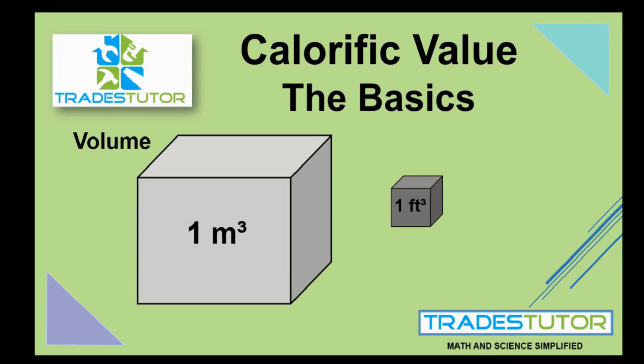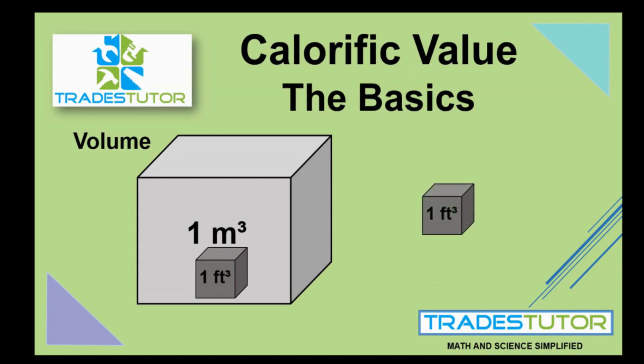Now, this little animation here — these pictures show you that a cubic meter is a lot bigger than a cubic foot, and we know that. But this becomes confusing when we get to calorific values and how to work with it. What you'll see is a cubic foot fits inside a cubic meter. The question is: how many cubic feet fit inside a cubic meter? Well, as it turns out, one cubic meter is equal to 35.31 cubic feet, meaning it's that much larger. So that's our first variable.